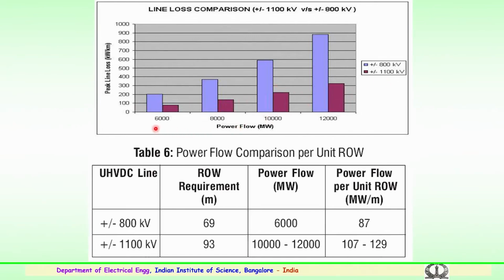You can see that as the power rating of the transmission system goes higher and higher, there will be a reduction in the peak line losses for the various power transmission levels. For 6,000 megawatts, the value is 50% of the 800 kV. Similarly, it is 30 to 40% in the case of 8,000 megawatts, and for 10,000 you can see it is 30%. In the case of 12,000 megawatts, you can see the line losses are much lesser than those occurring at the 800 kV HVDC line. So, this very clearly points out that going in for a very high voltage DC line will be much more economical to transfer a large amount of power over long distances.